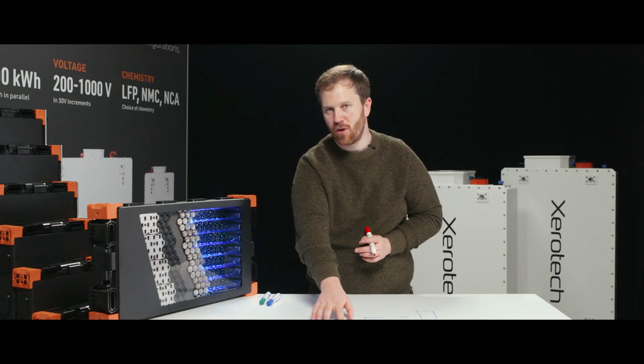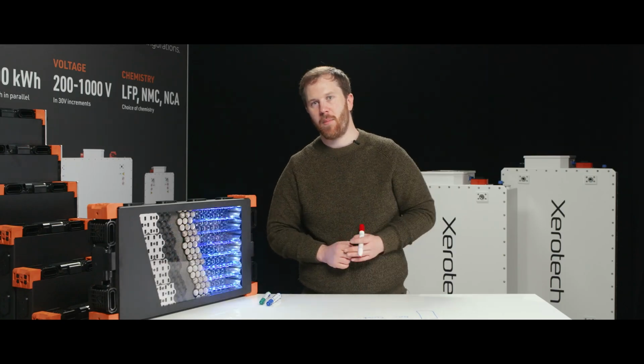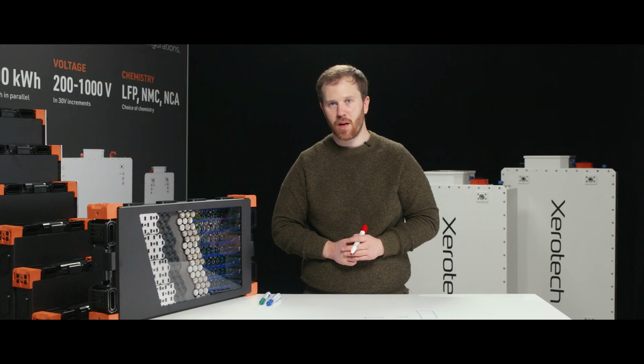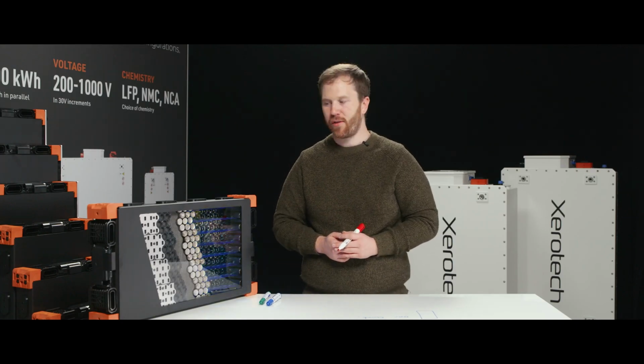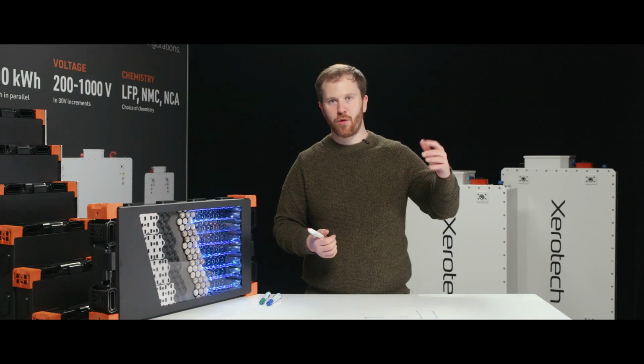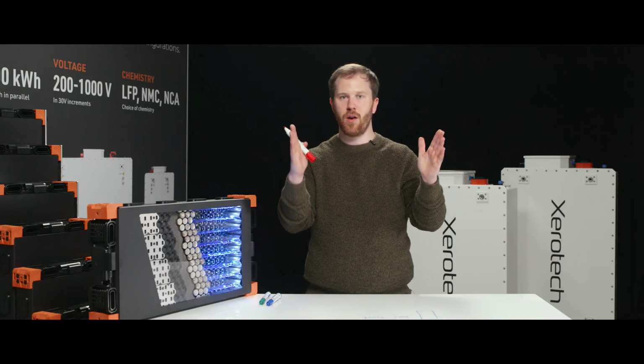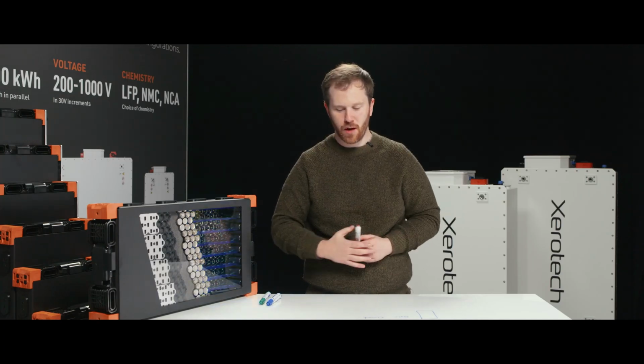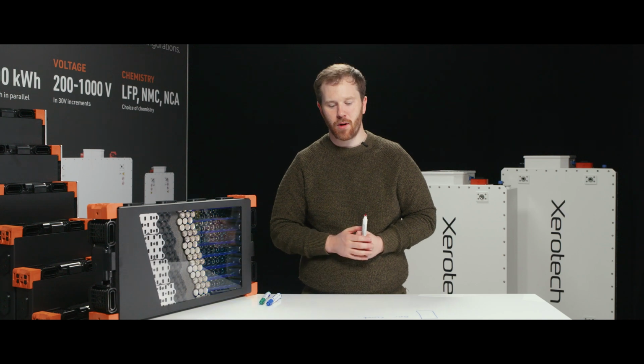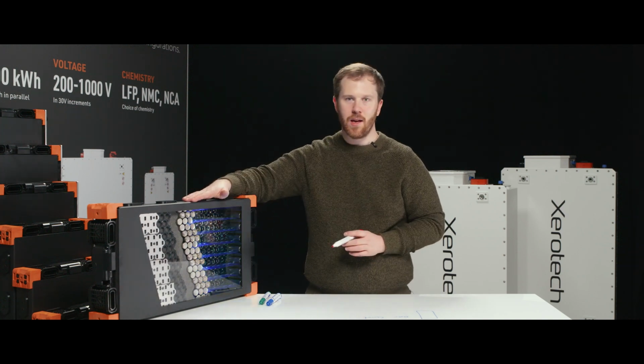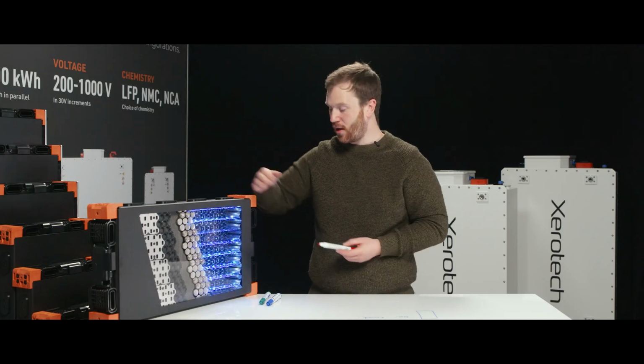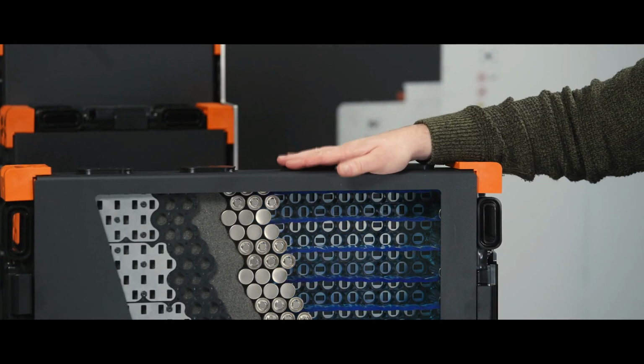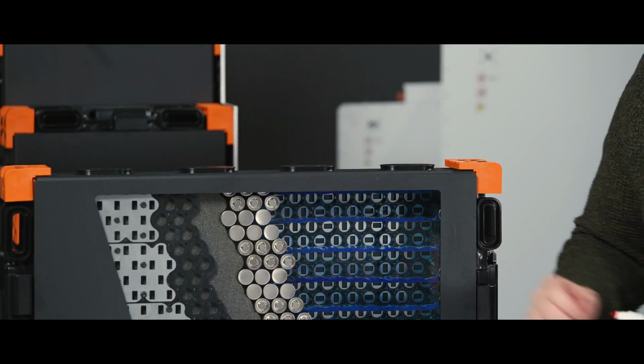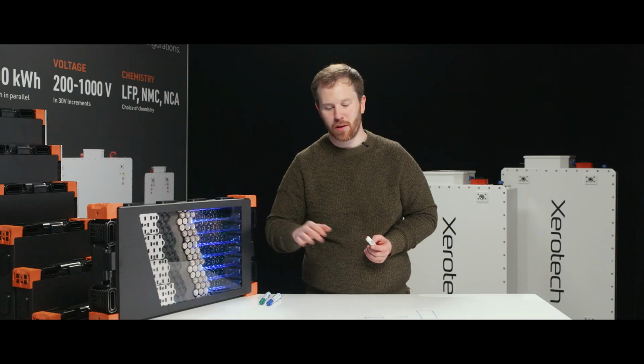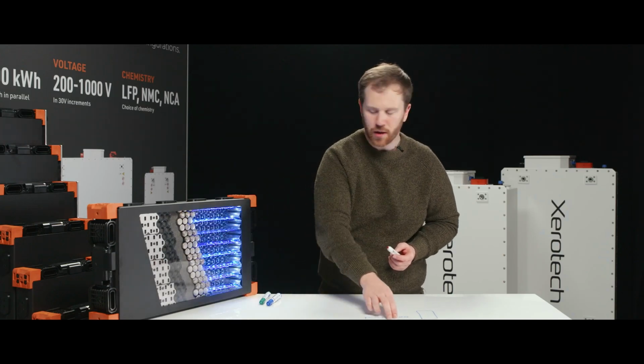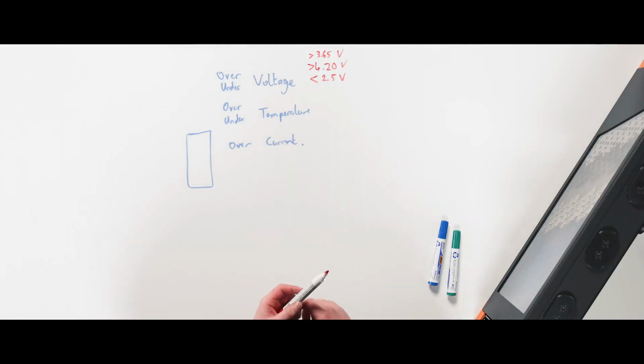And where you can run into danger and difficulty is recharging a battery cell that has been deeply discharged. That could lead to certain fire risks like dendrite growth, which are basically Christmas trees that grow from one side of the battery to the other through the separator, creating an internal short circuit. So voltage protection is incredibly important. And that actually is one of the things that a CMU or a cell management unit or a slave BMS does on a battery module. It's monitoring voltage, and it also does a little bit of housekeeping when it comes to voltage, but we'll come back to that. The next piece when it comes to a module is over temperature and under temperature.